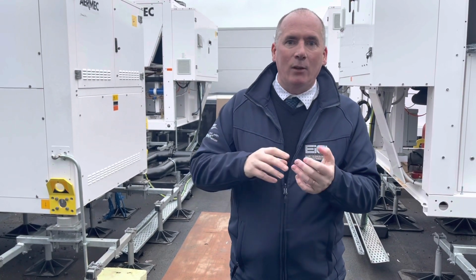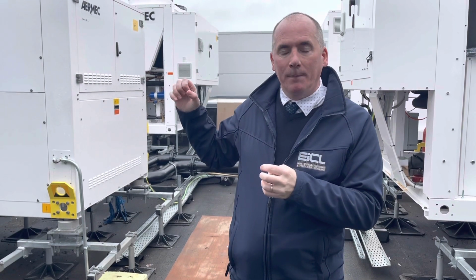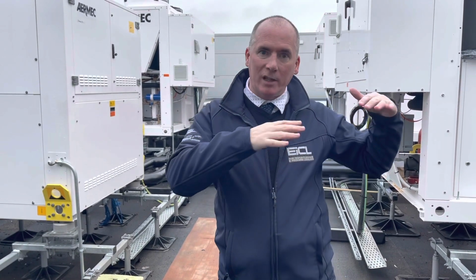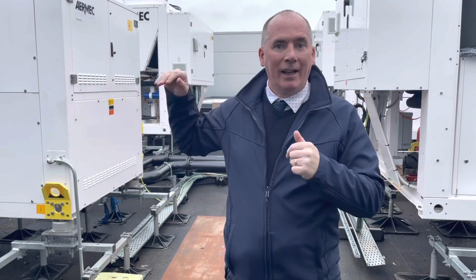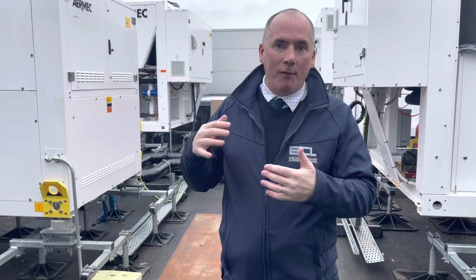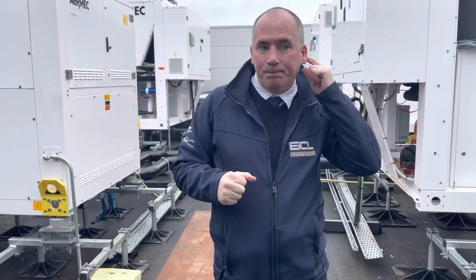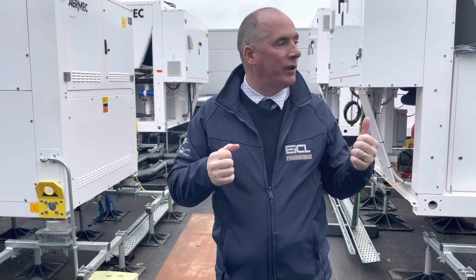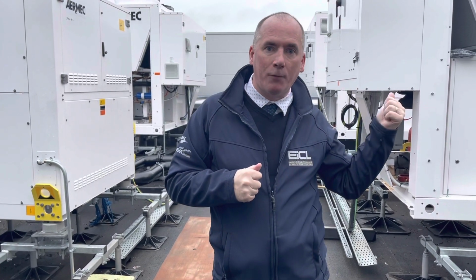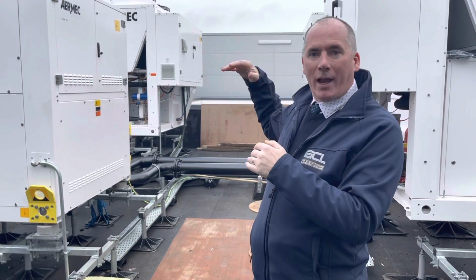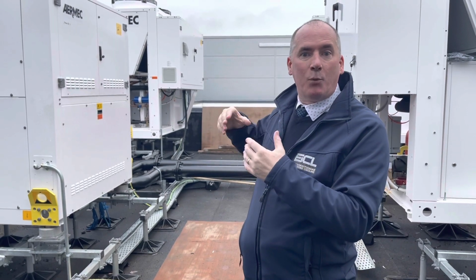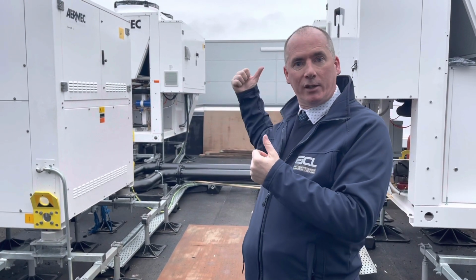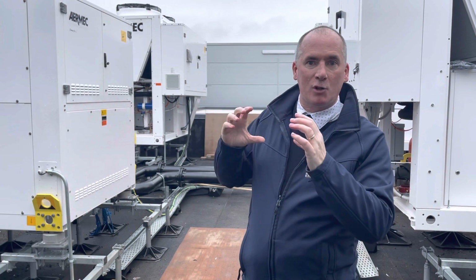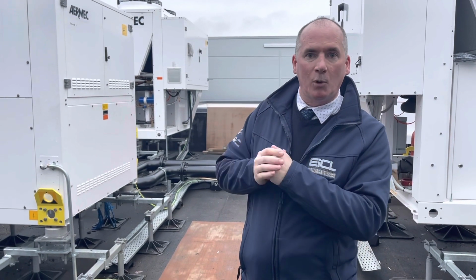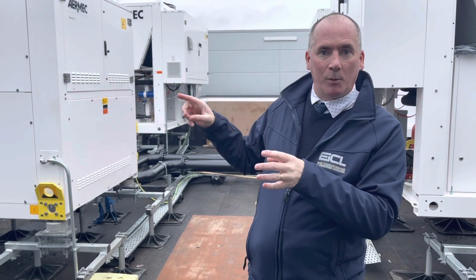On top of that then, what we have is a WWB. From a design perspective, you want to keep the heating temperatures as low as possible and the cooling temperatures as high as possible, with consideration for the design criteria. But what we've done here is we have a set point, I think 45-40, and then we have the WWBs, which is a water-to-water booster. They're inside. We'll go inside in a minute and get a visual on that. It's a bit noisy, so there probably won't be any audio, but we'll show you the WWB.